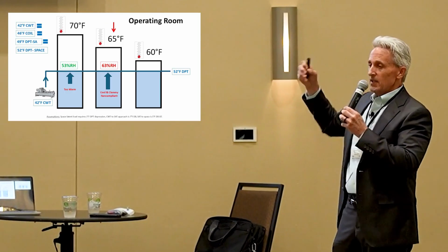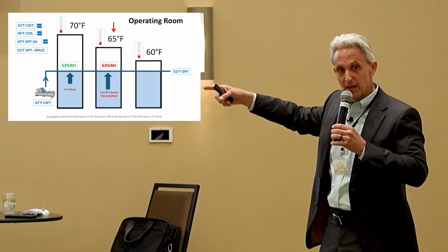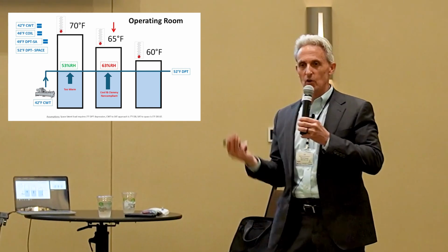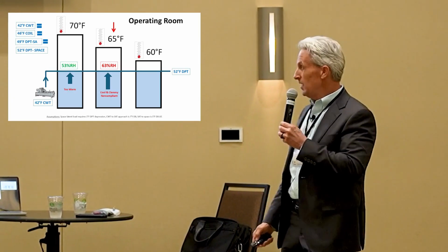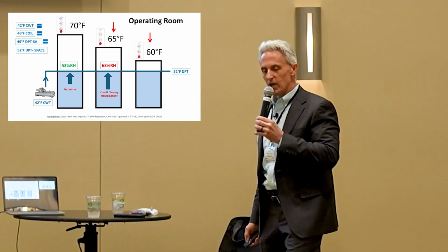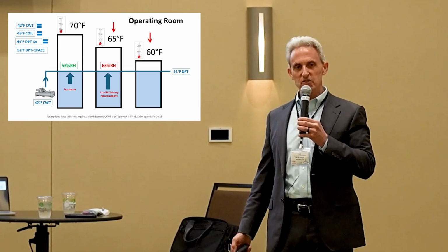Now, Doc still isn't comfortable. Doc's probably worse off than he or she was when we started at the higher temperature and the lower relative humidity. So the complaints are still coming. Doc wants it colder. So what do you do as a good facilities manager? You make it colder. You lower the temperature to 60 degrees Fahrenheit, and in fact, you make it so cold in that OR that you could hang meat, right? It's a meat locker, and Doc still isn't happy. What happens to the relative humidity?